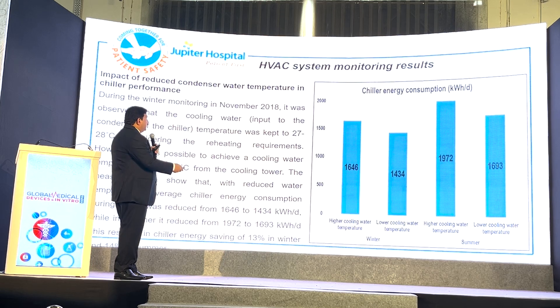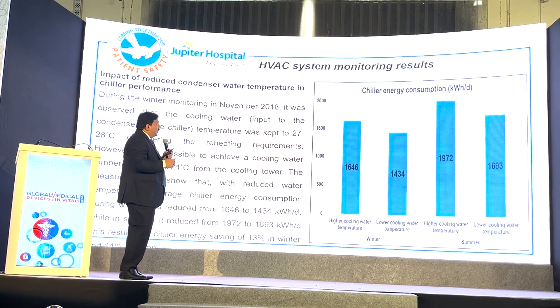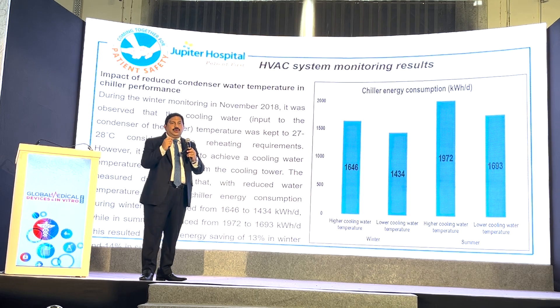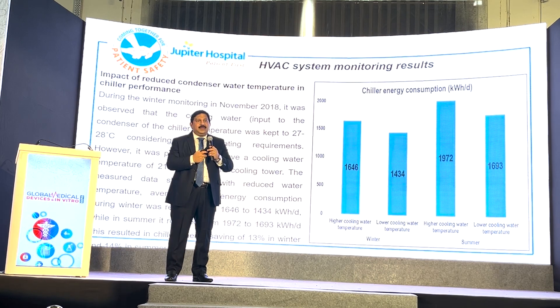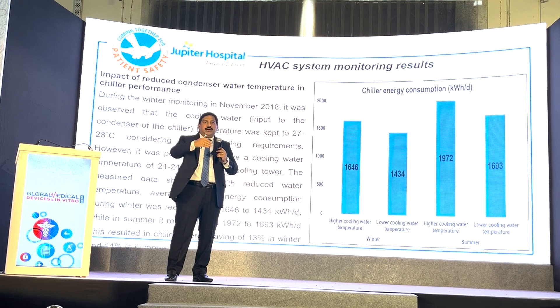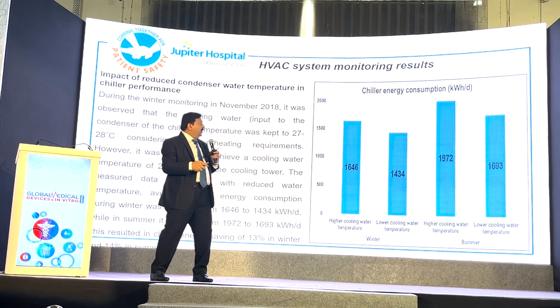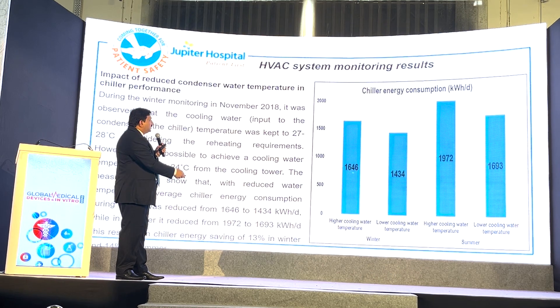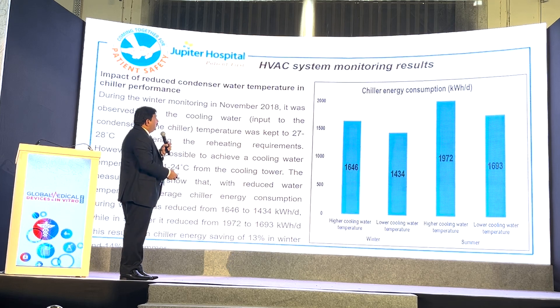You can see here — the chiller energy was higher due to higher cooling water temperature. If you see, on the condenser side we normally design 28 or 30 degrees — if 28 then 33 comes back, if 30 then 35 comes back. How does this make a difference? When my cooling tower condenser water temperature is 30 degrees, my electrical consumption is 1646 units, but when it comes down it becomes 1434 — a difference of about 200 units per day. Similarly, around 300 units per day difference in summer. If you can control your condenser water temperature, you can definitely save energy.